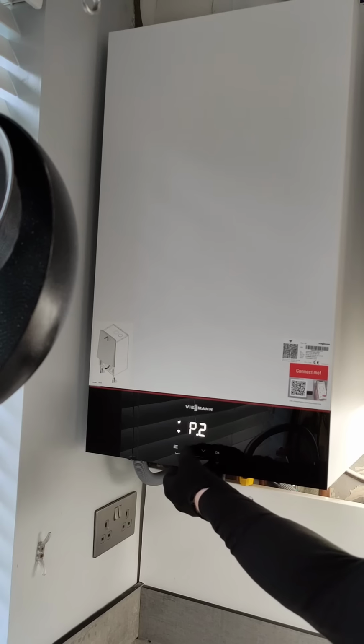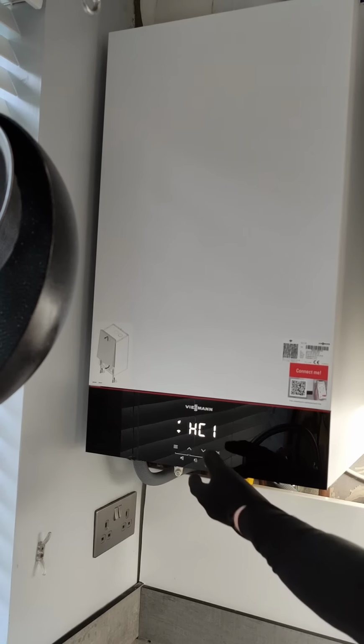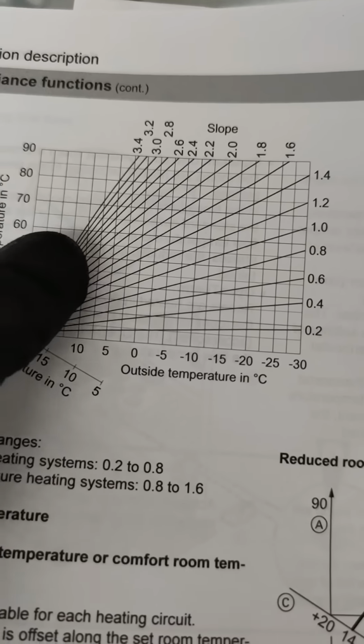So we go to P2, which is the heating curve, so we can go to heating curve 1. This is the weather comp heating curve. The better the building is insulated, the lower that number can be. If we have a look at the graph, if we look at the outdoor temperature of 10 degrees, and follow on the graph, if we've got the slope at 1.4, the radiators will be just over 30 degrees. And the higher the slope we set, so if we had the slope all the way up to 3.4, at 10 degrees our radiators would be about 60 degrees.